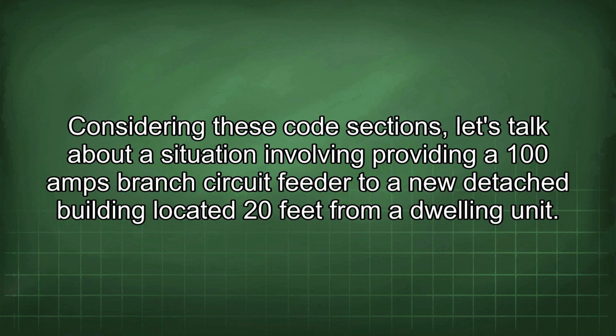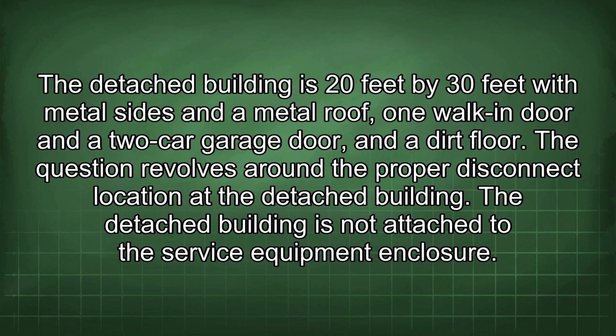Considering these code sections, let's talk about a situation involving providing a 100 amp branch circuit feeder to a new detached building located 20 feet from a dwelling unit. The detached building is 20 feet by 30 feet with metal sides and a metal roof, one walk-in door and a two-car garage door, and a dirt floor. The question revolves around the proper disconnect location at the detached building.